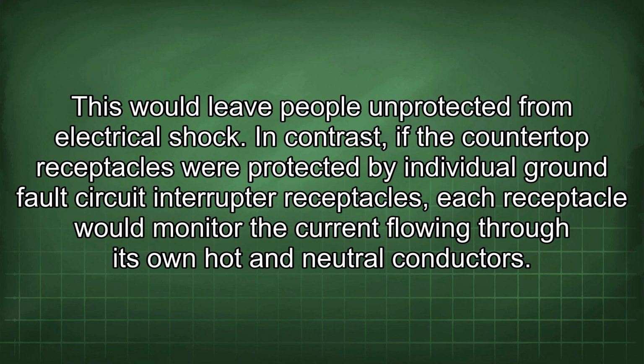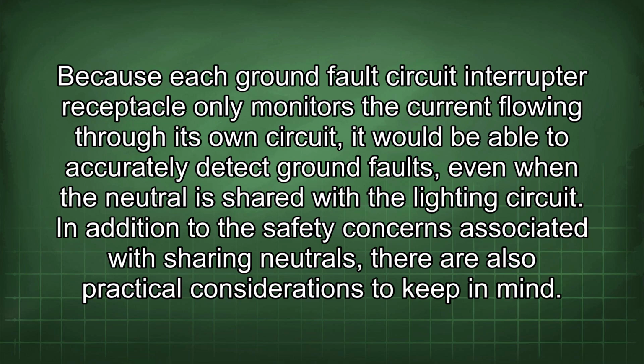In contrast, if the countertop receptacles were protected by individual ground fault circuit interrupter receptacles, each receptacle would monitor the current flowing through its own hot and neutral conductors. Because each ground fault circuit interrupter receptacle only monitors the current flowing through its own circuit, it would be able to accurately detect ground faults, even when the neutral is shared with the lighting circuit.